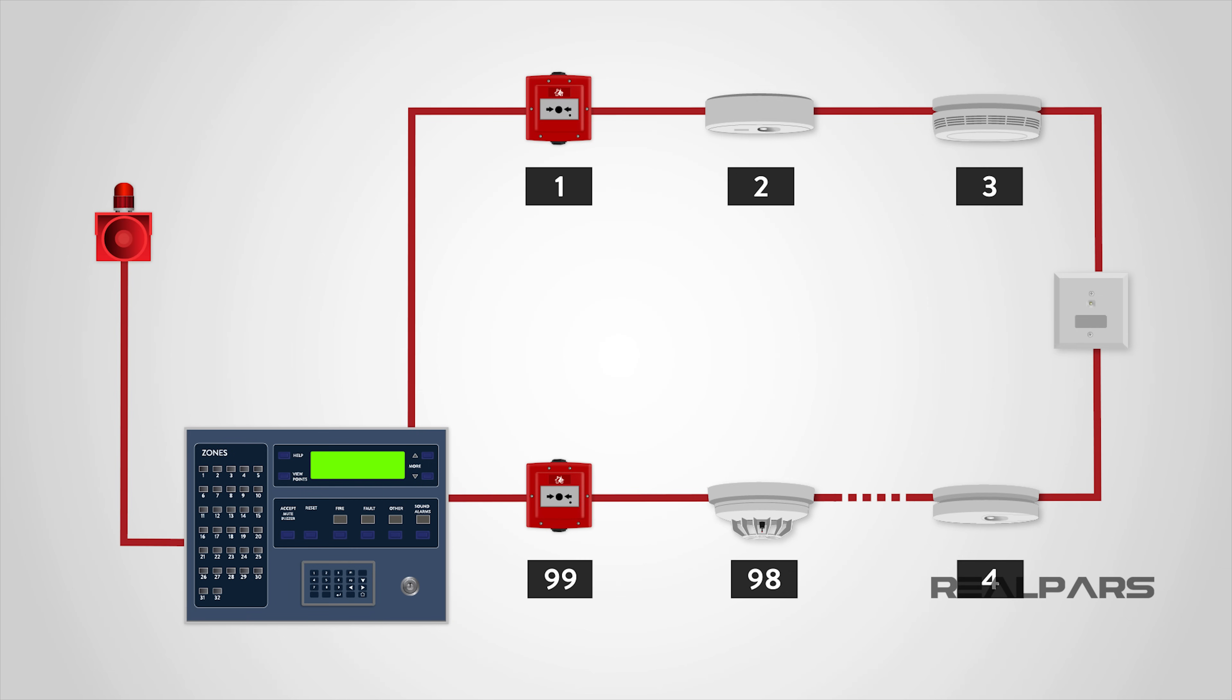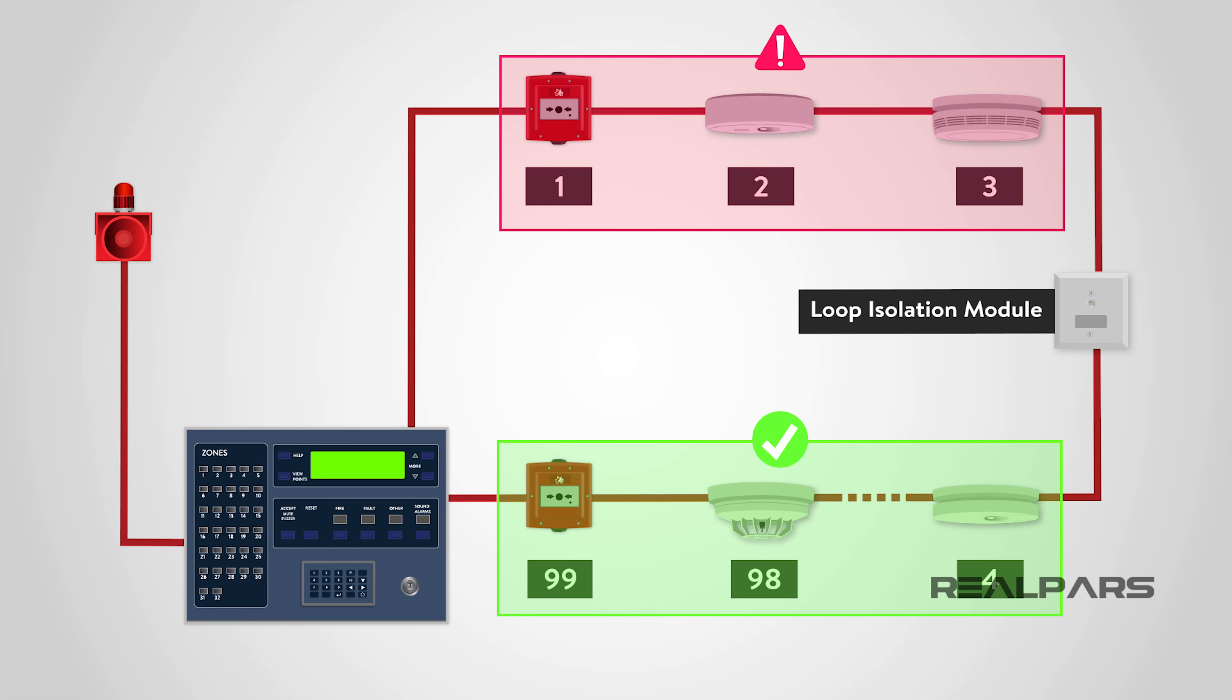It is common for the loop to be fitted with loop isolation modules, so that the loop is sectioned in order to ensure that a short circuit or single fault will only cause the loss of a small part of the system, allowing the rest of the system to function normally.